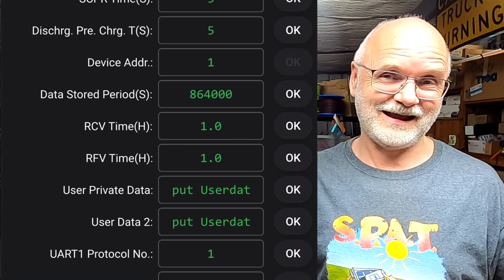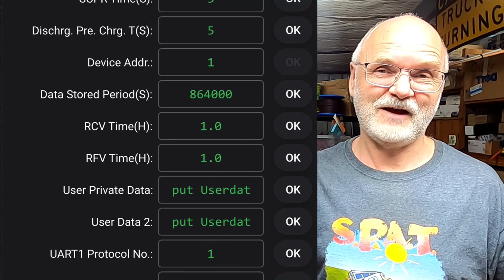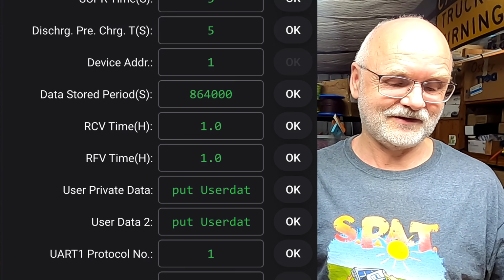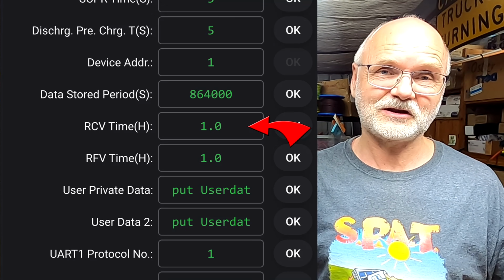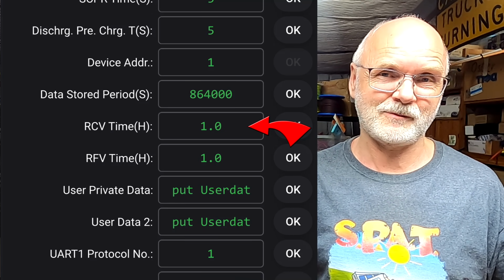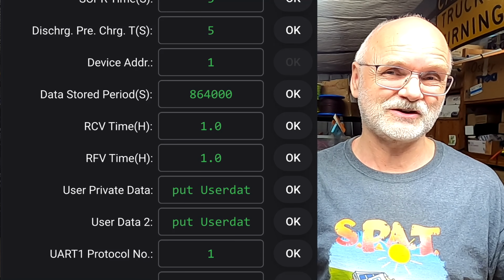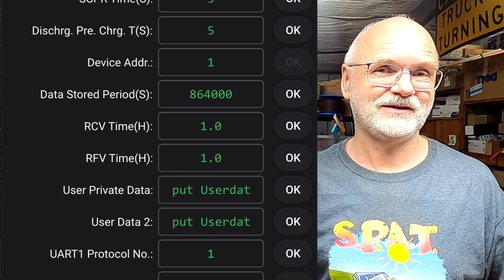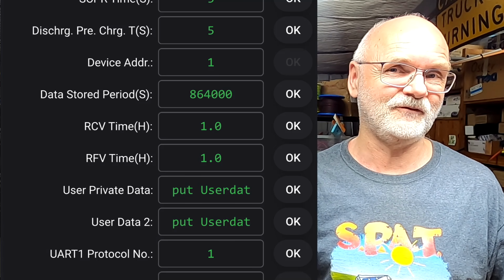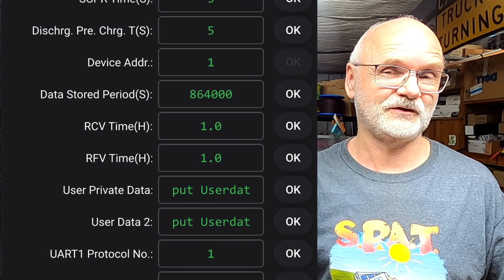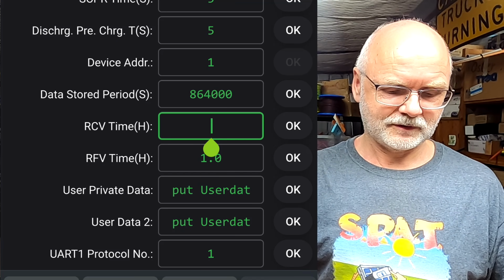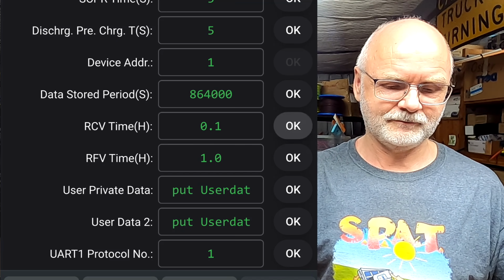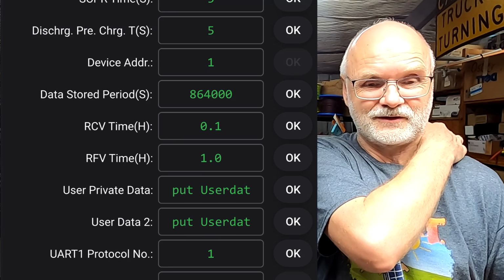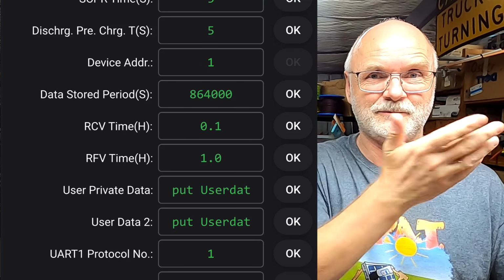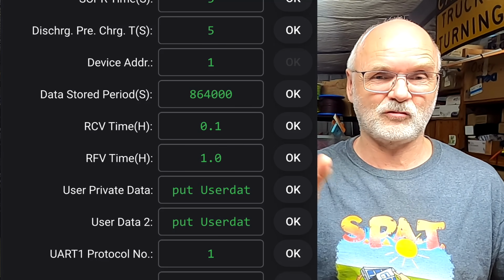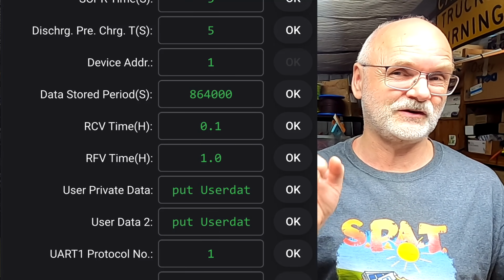So boys and girls, now we have 2 brand new features here, which we have requested for quite a while. The first one is the RCV timer. So basically this timer here is an absorption timer. We can now set an absorption time. How long will the BMS tell the inverter to keep the RCV, your requested charge voltage, or the CVL? It sits on 1 hour. You can go down to 0.1, click OK, and it still accepts it. So 0.1 of an hour is 6 minutes, right? So in 6 minute increments, you can set your absorption time now.